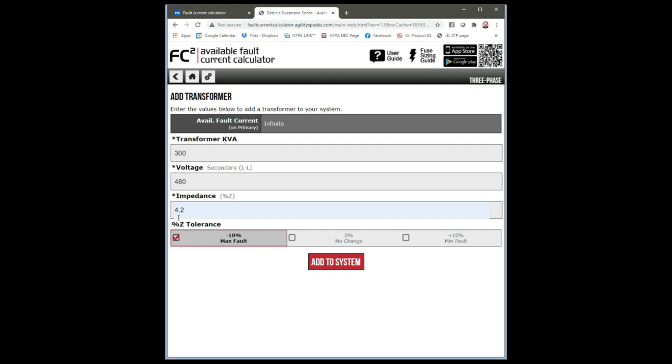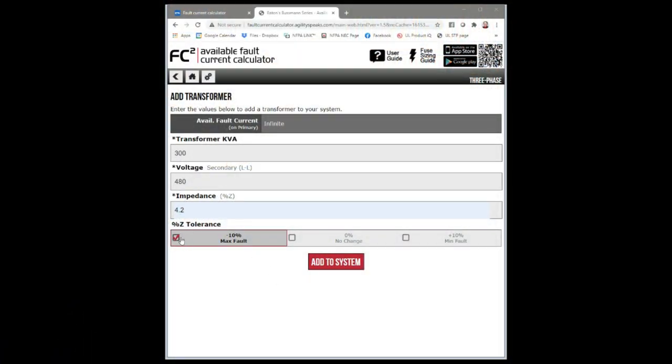Transformer kVA is 300, line-to-line voltage is 480, and the percent impedance was 4.2. Down at the bottom you can see percentage Z tolerance: minus 10%, no change, minimum fault. When they test transformers and write 4.2% impedance, not every identical transformer is going to be precisely 4.2% - there are tiny variations. You're allowed to go plus or minus 10% of your marked impedance. So when doing this design, I'm going to assume a 10% maximum fault because that gives the worst case scenario.